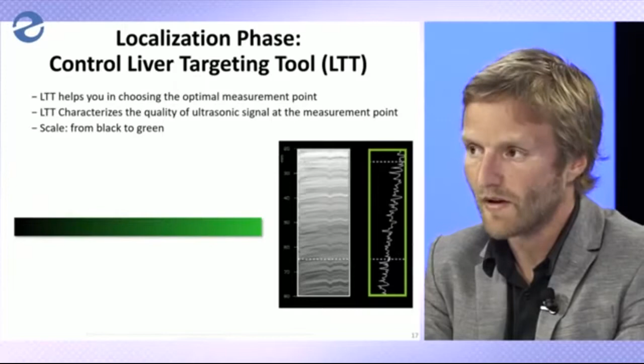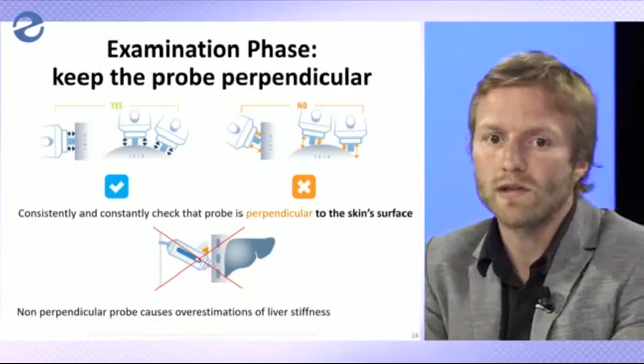Last thing, as some of you might already know, is the importance of keeping the probe perpendicular. When we say perpendicular, it's perpendicular to the patient's skin. So it's really important to keep the probe perpendicular to the skin, otherwise there is a risk that the stiffness value is slightly overestimated. It's really important to keep the probe perpendicular for your 10 measurements and not only for the first 2 or 3 measurements, otherwise there is a risk for you to see your values increasing a little bit.